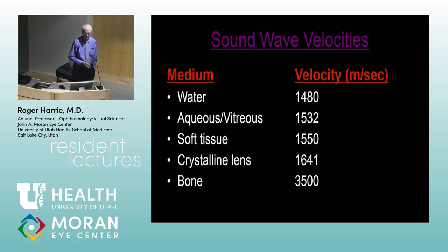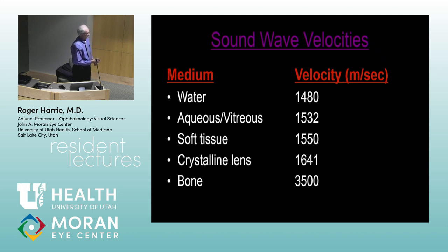Sound wave velocity: the denser the media, the faster the ultrasound velocity. Water is about 1480, aqueous and vitreous is 1532 — that's kind of the standard setting for most ultrasound biometers. To really refine it, a lot of people break it down separately for the aqueous, vitreous, and lens, and add those together in a formula to get the true axial length. But with a standard biometer, 1532 is your average setting.